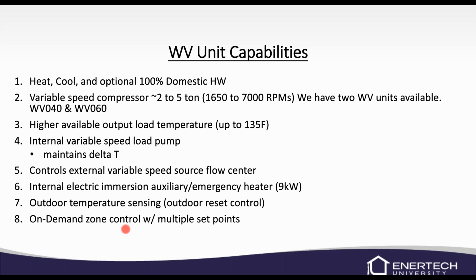There is an internal electric immersion heater. It's a 9 kilowatt heater, and it's used for supplemental or backup. If for some reason the geothermal unit went down, we would have the backup heat. It does come with an outdoor temperature sensor that we will use for outdoor reset, and we'll talk about the outdoor reset a little bit later on. And we have on-demand controls with multiple set points.